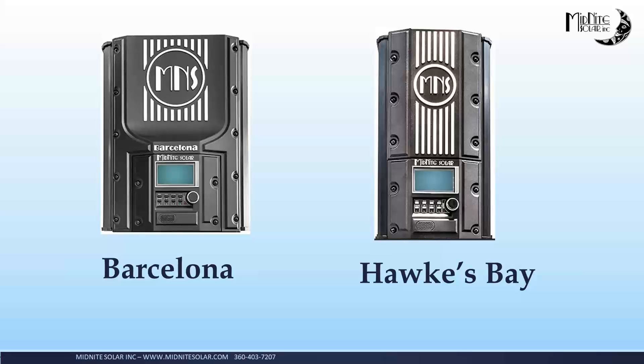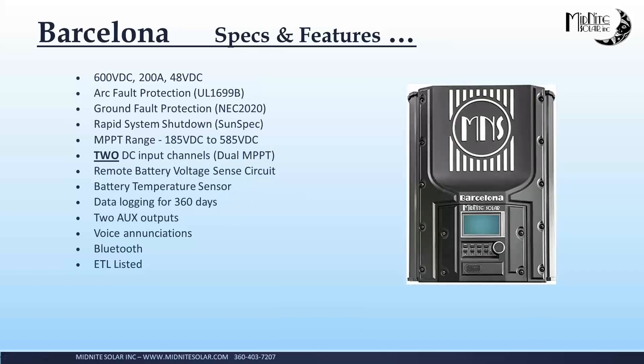So that's kind of it for the ROSE. We have two 600-volt charge controllers released: the Barcelona and the Hawke's Bay. They have all the same specs electrically except for the throughput. The Barcelona is possibly the world's biggest charge controller — 600-volt DC input, 200 amps out at 48-volt DC. It has dual MPPTs: two completely independent 100-amp MPPT modules inside. They will track from 185 to 585 volts DC. They also have remote battery voltage sense and battery temperature sense — you only need one in the system. If you had four Barcelonas and two ROSEs, only one battery temperature sensor and one remote battery voltage sense circuit is actually needed. We also offer ground fault protection as an optional module. The ground fault system in the Barcelona and Hawke's Bay uses differential current on PV leads to detect ground faults, so you can solidly ground the battery system and still get ground fault protection.